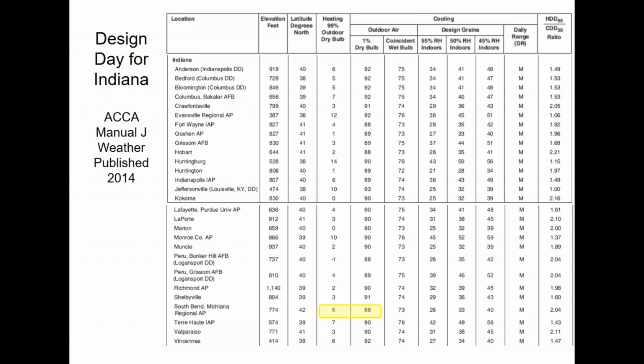On the cooling side of the equation, it works the same way. Instead of 99%, it says 1%, but it means the same thing. It's just because if you imagine a bell curve of all the temperature weather data for the year, 1% on this side, 99% on that side, it means the same thing. So 1% of the time, it'll be above 88 degrees in South Bend. Our code required design outdoor temperature for South Bend is 88 degrees.